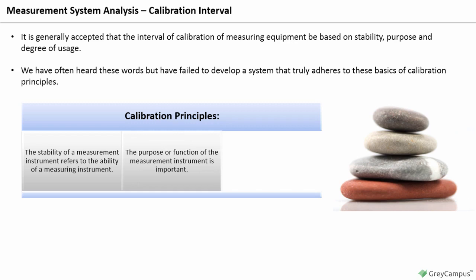The purpose or function of the measurement instrument is important. Whether it were to be used to measure doorstops or nuclear reactor cores would weigh heavily on calibration frequency decision. In general, the critical applications will increase frequency, and minor applications would decrease frequency.